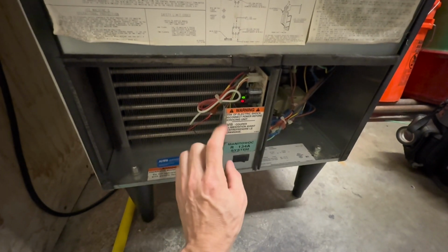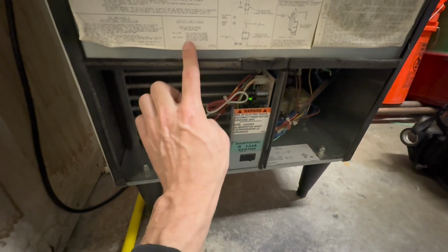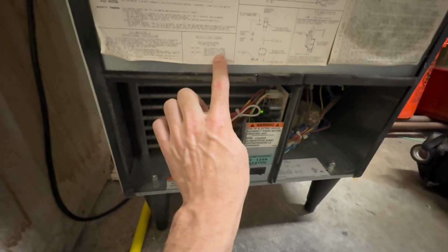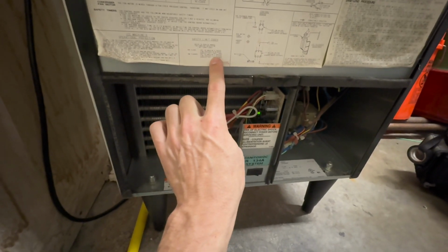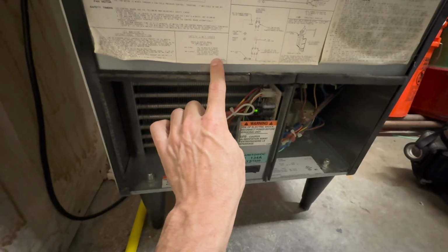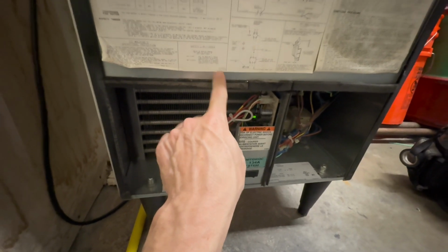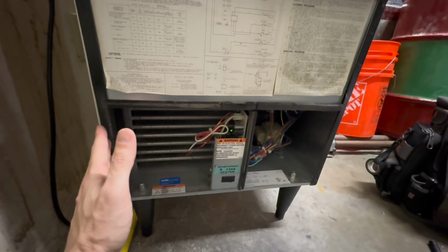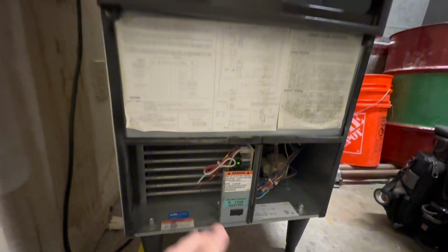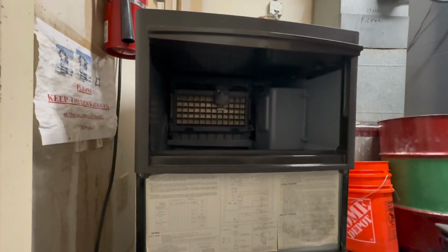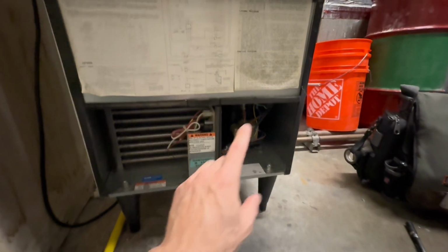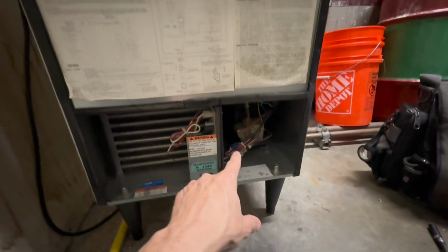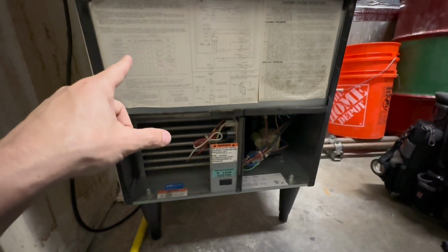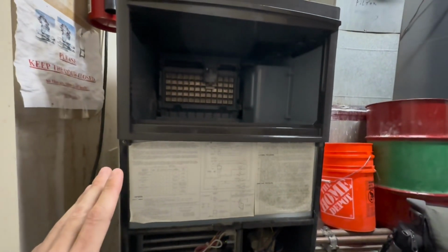So it flashed two times, which means, what does it say? My harvest time exceeded 3.5 minutes consecutively 3 times in a row. So that's what we're going to be looking at. Something's going on with our harvest. So the compressor just clicked on. We should be in pre-chill. We're just going to wait, see what happens from here. The fan has not come on yet.